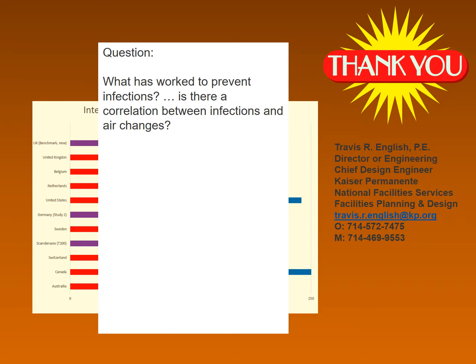There's no known relationship or correlation between really any ventilation variable and general infection rates. The exception to that, well, it's not really even an exception. Even in operating rooms, it's difficult to prove that a certain level of air cleanliness has a direct effect on surgical site infection rates. There are some studies that show lower surgical site infection rates under clean air regimes, and then there's some other studies that prove otherwise. If you're like me, you probably grew up with the belief that the general air change rates in the patient room are there to prevent infections, but that is unsupportable at any level.